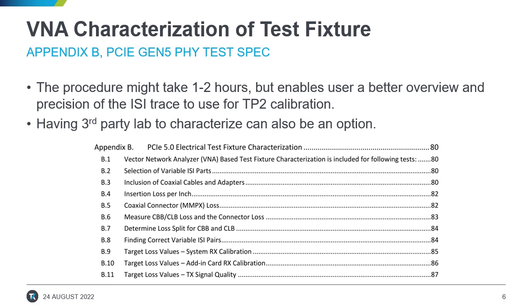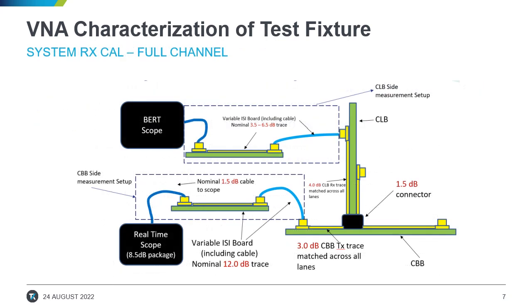We'll take a deeper look at the target loss values and the diagram that describes how we split the channel loss for the receiver calibration. Here's what the system RX cal full channel loss looks like. Note that for Gen5 we have a total loss of 34 to 37 dB. So for the system receiver cal, we have split for the CLB side, that is going to be 7.5 to 10.5 dB variable. On the CBB side, that's going to be 26.5 dB fixed.